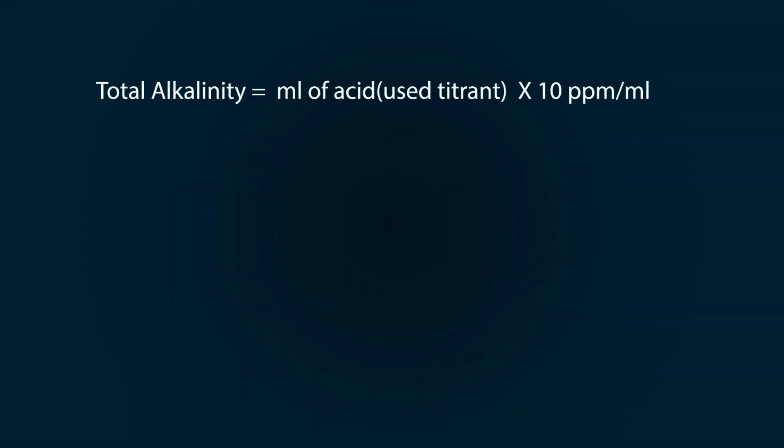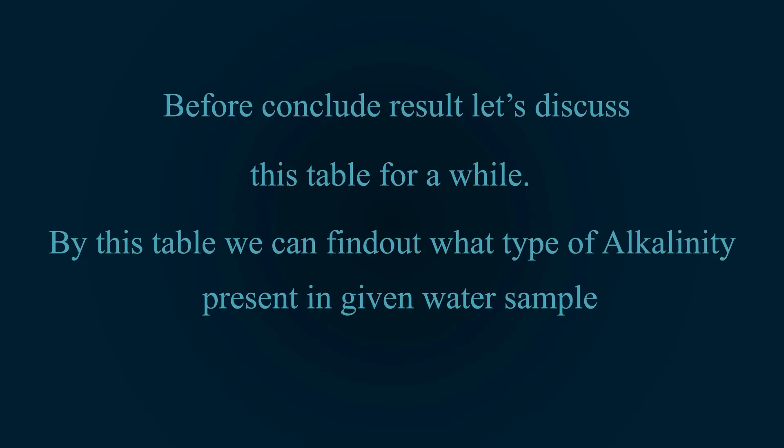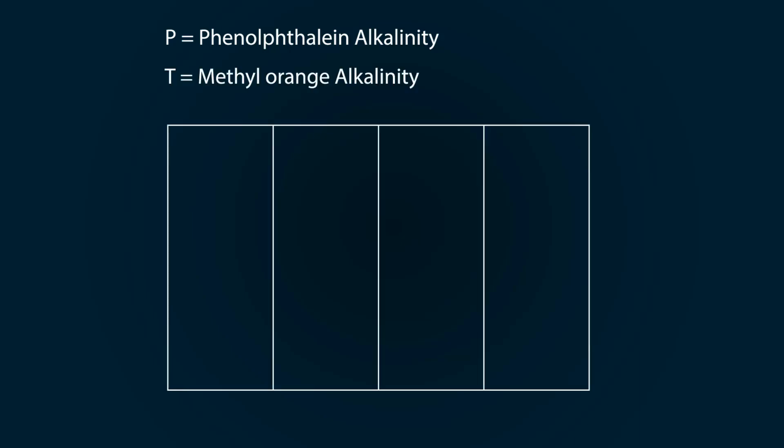For alkalinity, it has the same formula: ml of acid multiplied by 10. Methyl orange alkalinity will be 19.6 multiplied by 10 and we get our value as 196 ppm. Before concluding results, let's discuss a table through which you can get alkalinity of different water samples. P indicates phenolphthalein alkalinity and T indicates methyl orange alkalinity.